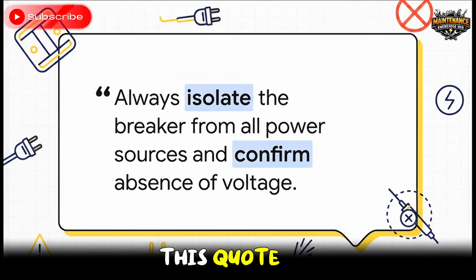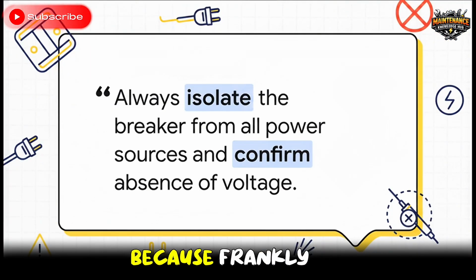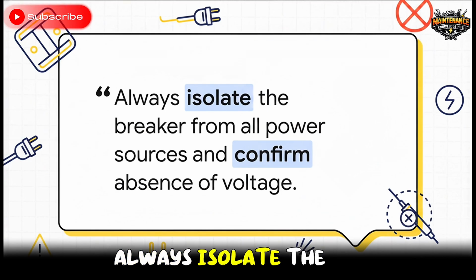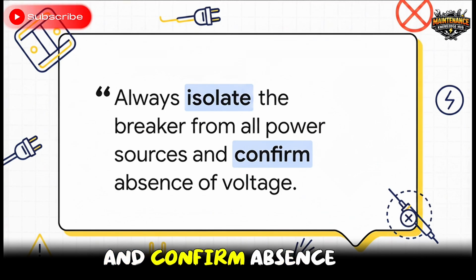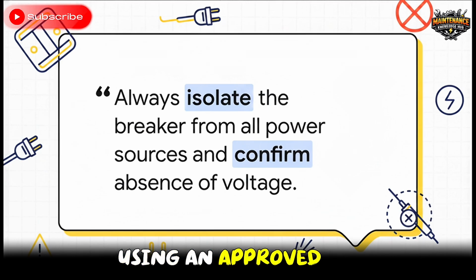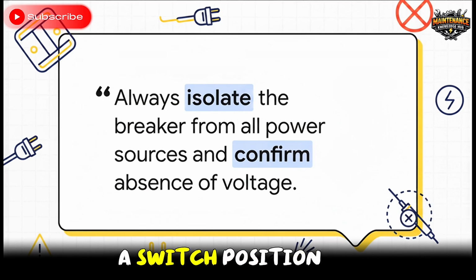I want to read this quote directly from the safety guidelines because, frankly, it is the golden rule of VCB maintenance. Always isolate the breaker from all power sources and confirm absence of voltage using an approved tester. Listen, never, ever assume a breaker is dead just based on a switch position.